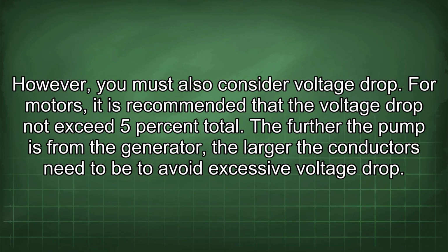However, you must also consider voltage drop. For motors, it is recommended that the voltage drop not exceed 5% total. The further the pump is from the generator, the larger the conductors need to be to avoid excessive voltage drop.